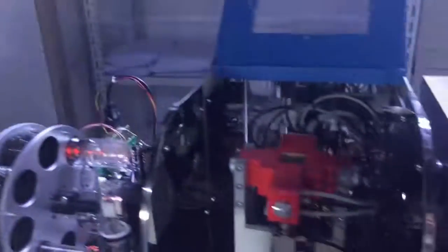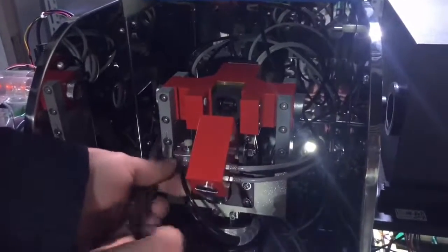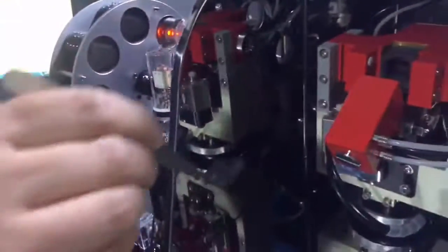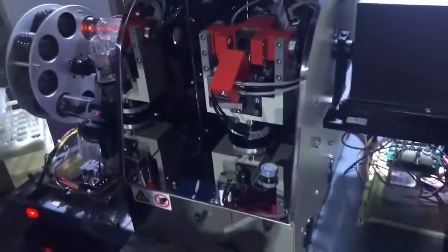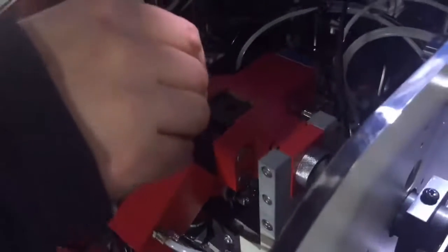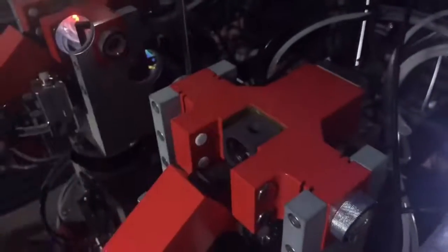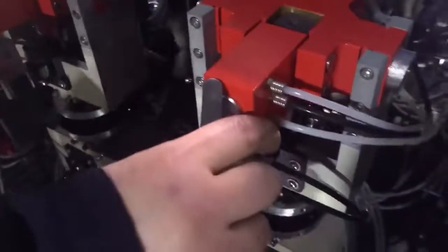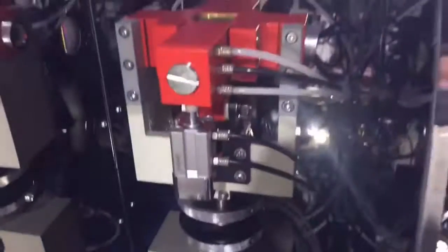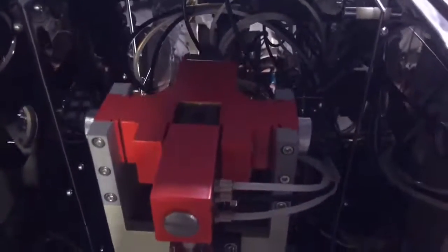Click Graphite Tube button in the software, and then remove the bracket. You could insert the graphite tube into the graphite furnace. Do not touch the graphite tube directly by your hand. It's recommended to use tweezers to put the tube into the furnace, and then push the bracket back and click OK button. The position will be located.